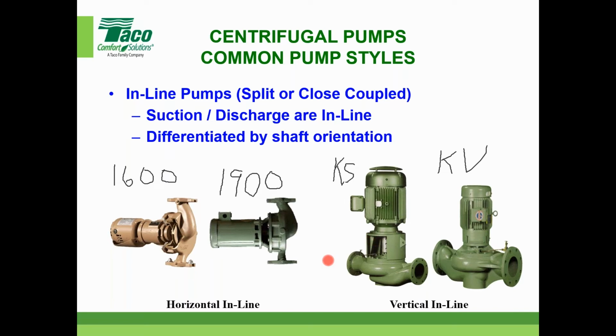People ask what applications should use a base mounted pump versus an inline pump, the verticals. A big part of our business is the FI, CI line and the KV-KS line. It's a difficult question because all four are good for all applications: heating systems, hot water systems, condenser water systems. It's really personal choice. Maybe your office has always done base mounted pumps, so you stick with those, and someone else may use verticals instead. It's really a crossover from an application standpoint, a personal choice.